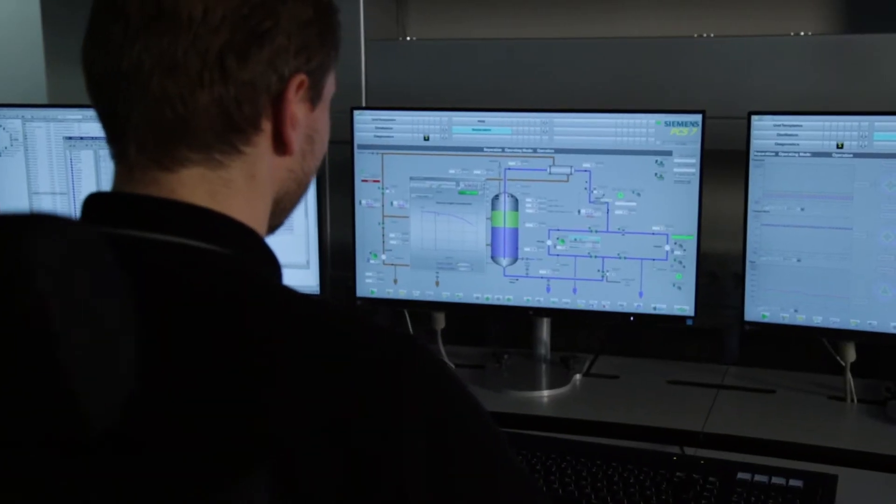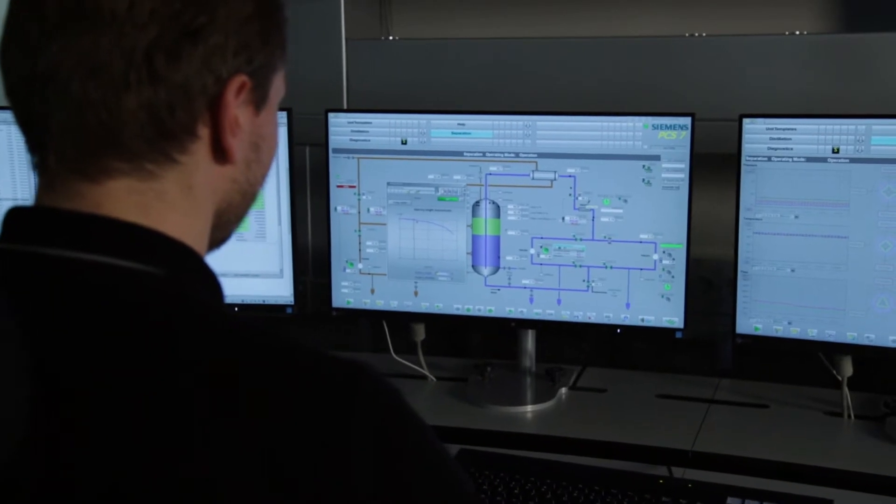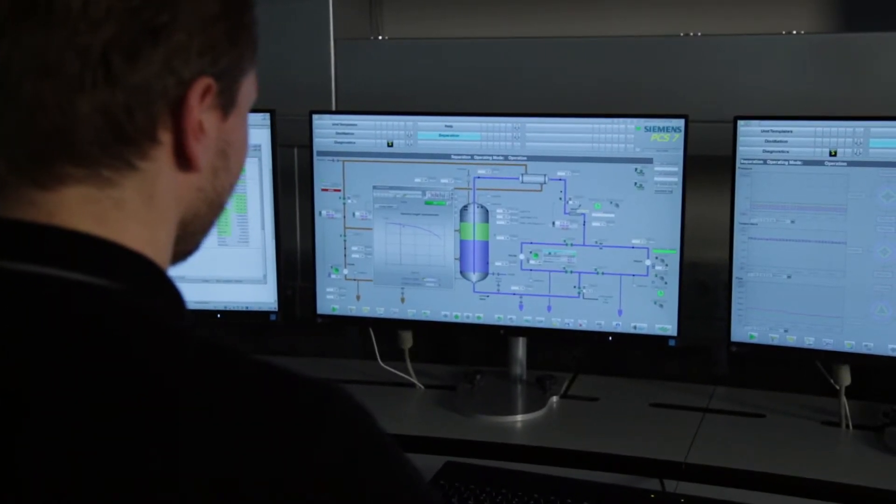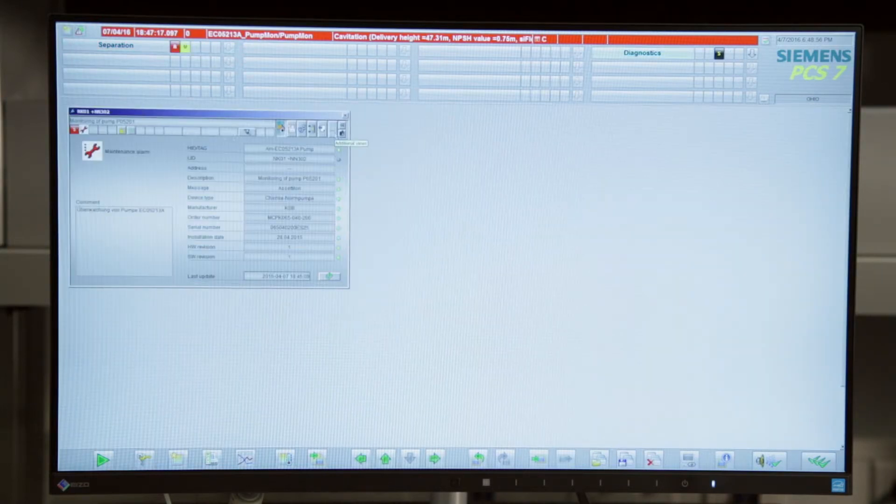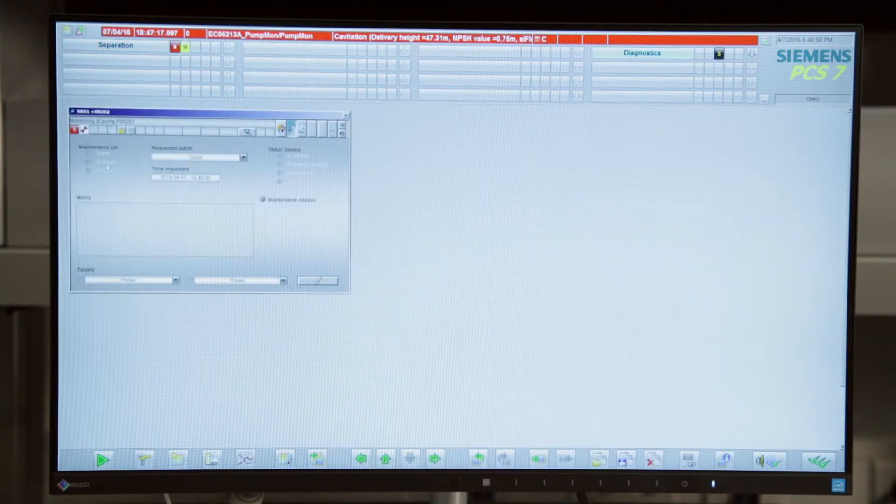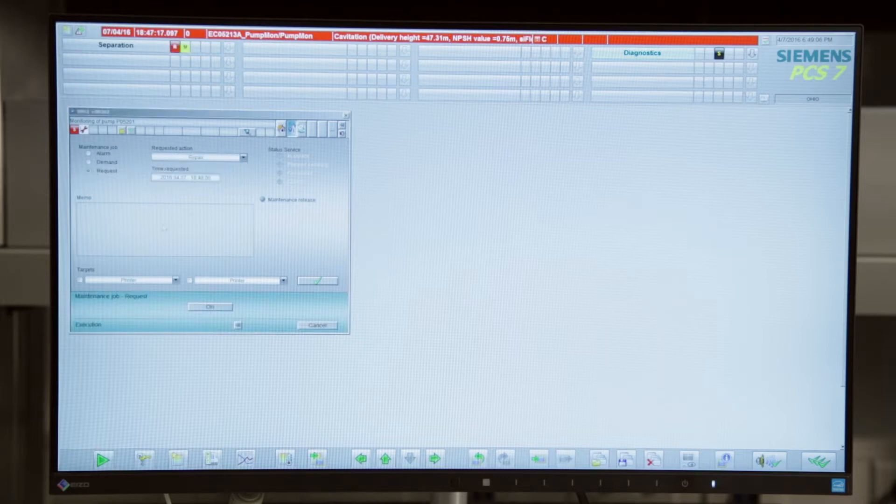Thanks to the continuous monitoring in the SIMATIC PCS7 process control system, an NPSH value below the curve will be registered and reported after a certain period of time. This minimizes the risk of pump failure if serviced in a timely manner.